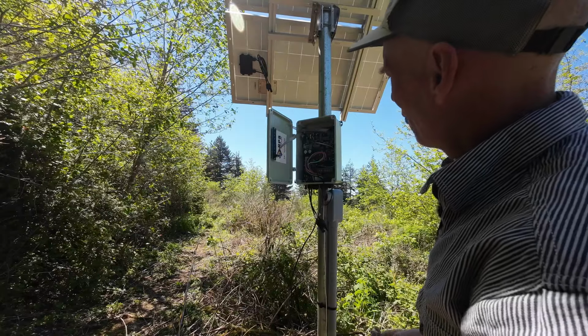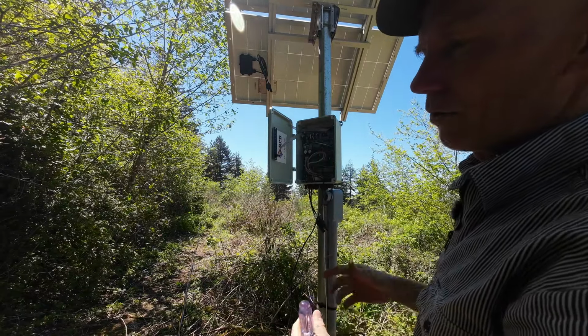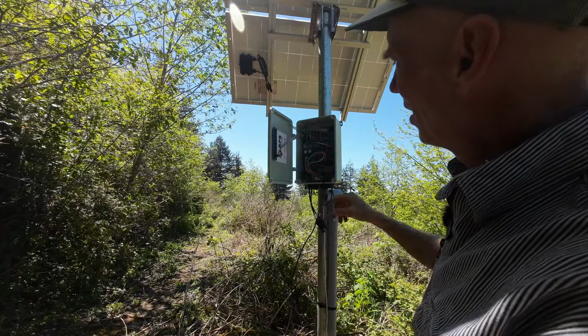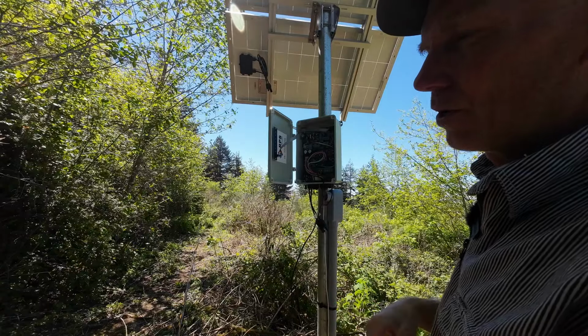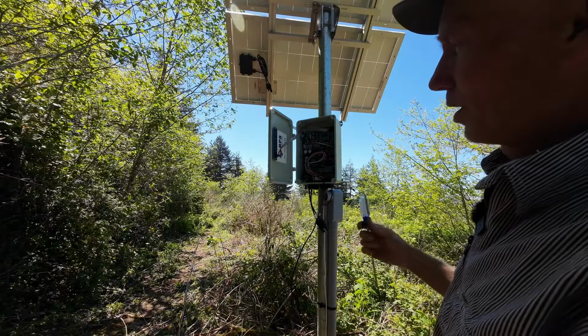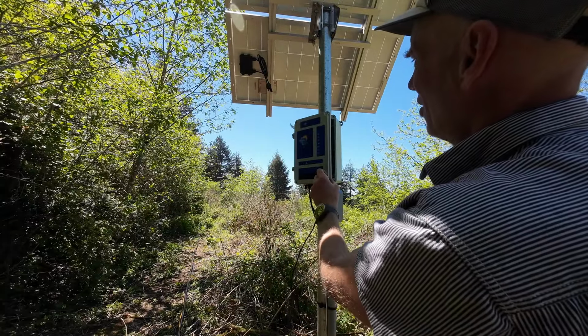There, so that should be it for the wiring. There are only 2 controls in here. One is a timer for how long, when the well goes low, it waits before it tries to spin up again and go. And then there's one for the overall speed of the pump. We'll probably run this pump pretty slow because we don't have a lot of sun and we have a slow well, and that's where we're gonna use a giant tank to fill it up. So with the exception of that wire, this should be ready for testing.